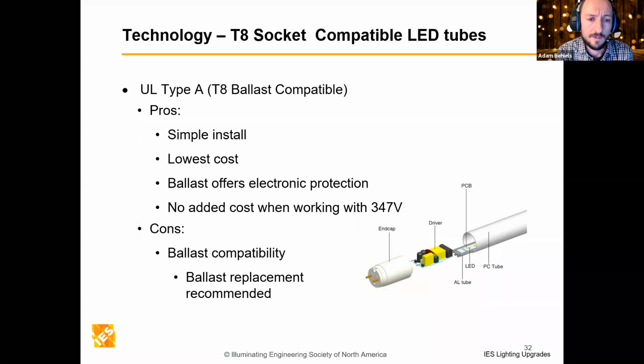So UL type A, although they are ballast compatible, they still do have an internal driver that is powered from the high frequency output of the ballast. If you're not changing out the ballast, make sure the lamp is compatible with the existing one. Ballast compatibility is getting a lot better over time, but it's still worth checking that the combination you're working towards is going to be compatible. It may be a good thing to change the ballast either way, just so that you're giving a good lifespan to the new install. And with the cost of these tubes, it can still be quite a good payback even when you're replacing ballasts as well.